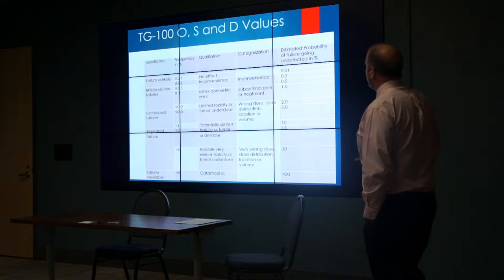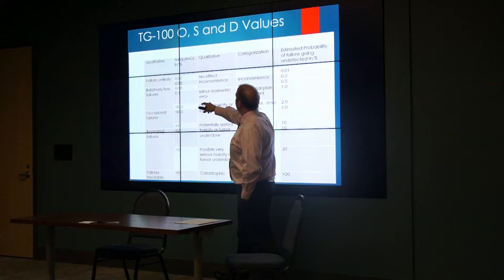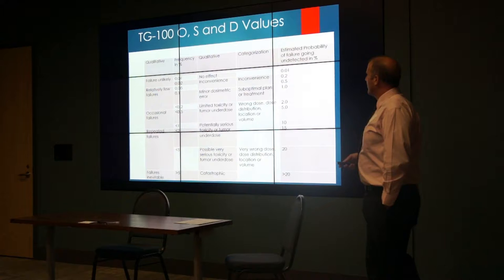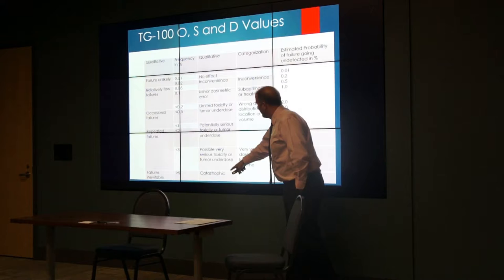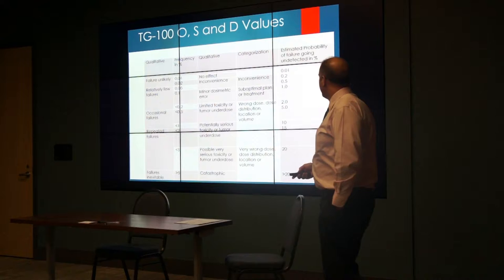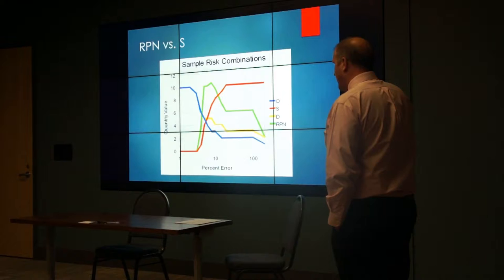This is a table from TG-100 showing exactly how these numbers are assigned, in 10 rows. For example, a probability or occurrence of 1 would be a probability of 0.01%, or 1 in 10,000 probability of occurring. A severity of 1 would have no effect, ranging all the way to 10 which would be catastrophic. The probability of going undetected ranges from 0.01 also to greater than 20% not being detected as it goes through the steps.